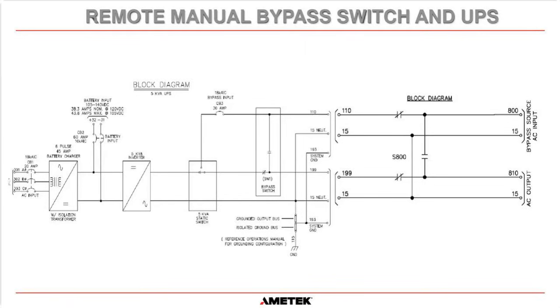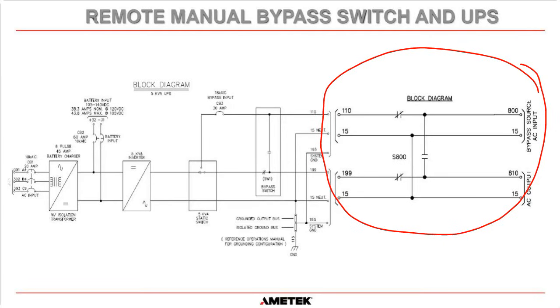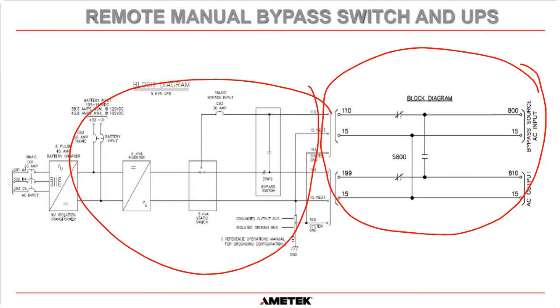And then there is a slight difference between a manual bypass switch that is connected on the UPS itself and what is called a remote manual bypass switch. And specifically, I'm going to discuss an AMETEK Solidstate Controls remote bypass switch. This portion here is an AMETEK Solidstate Controls bypass switch, and this section here is an AMETEK Solidstate Controls UPS.